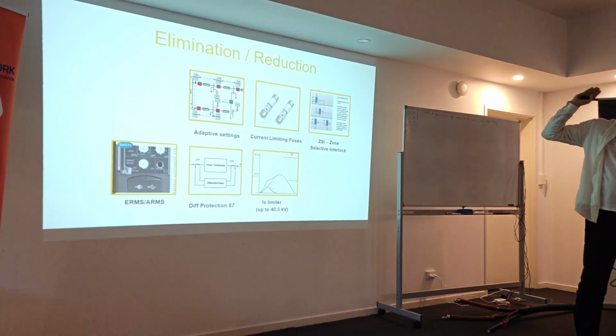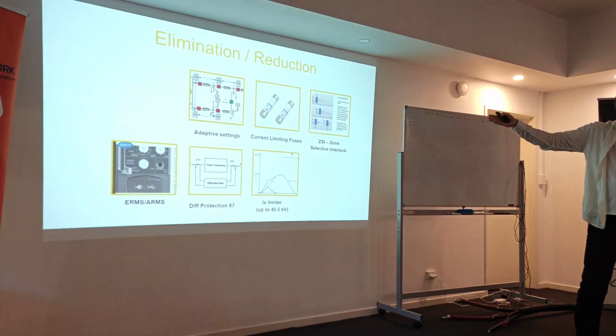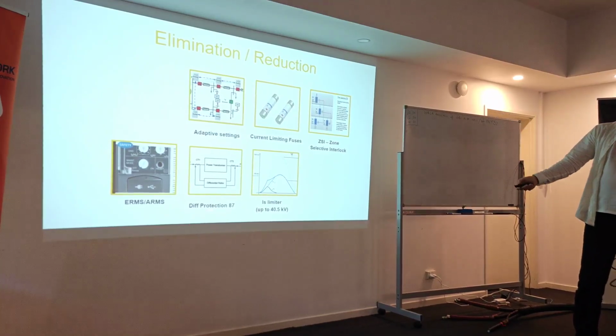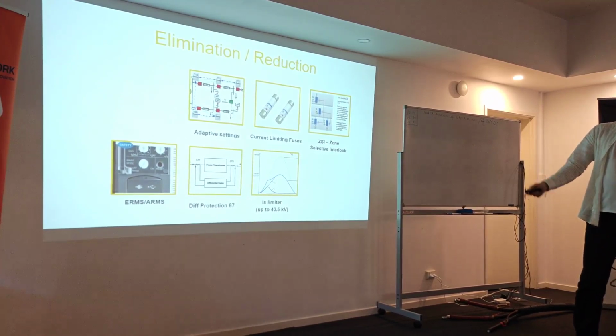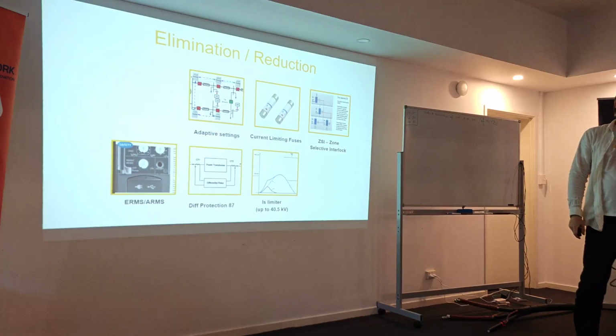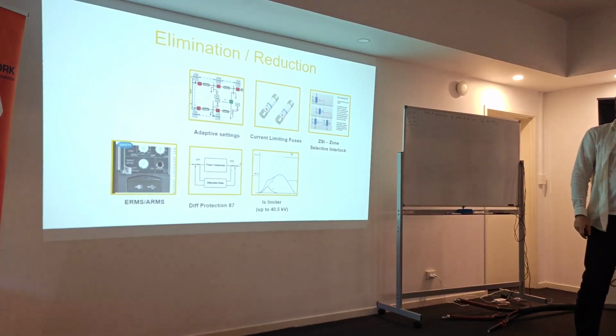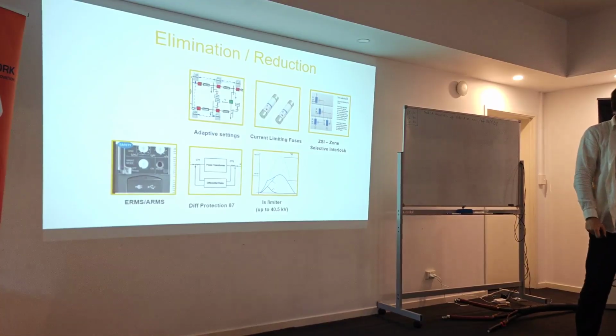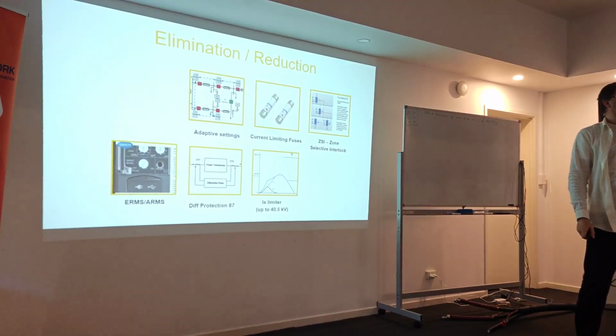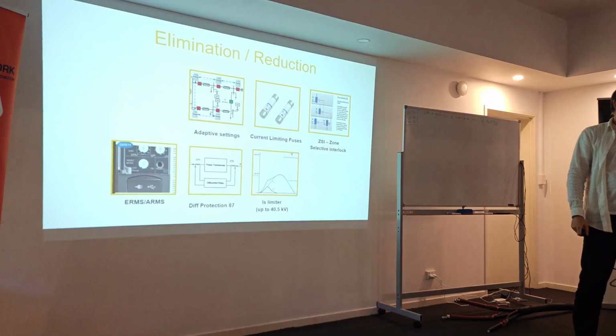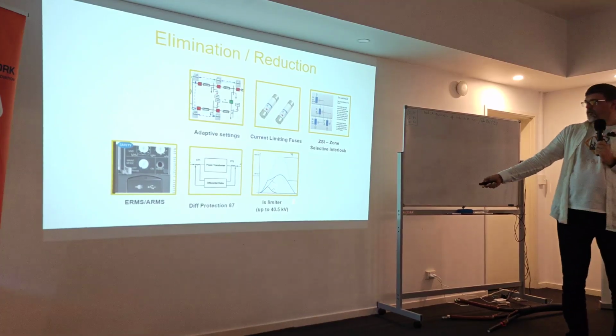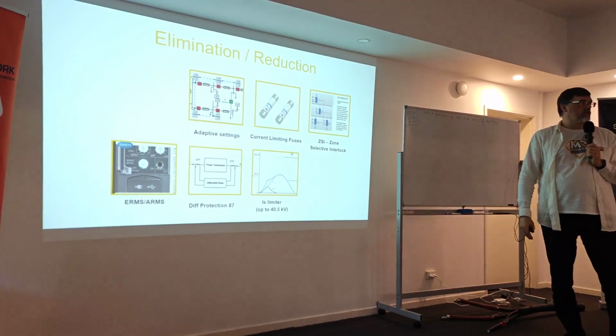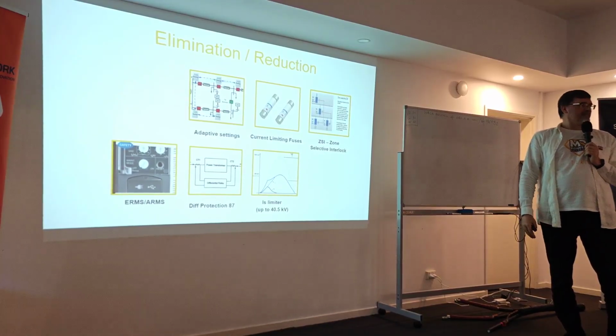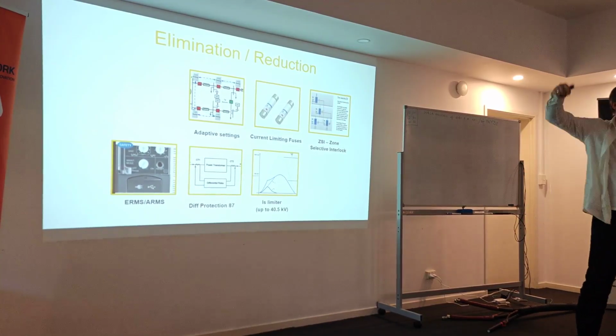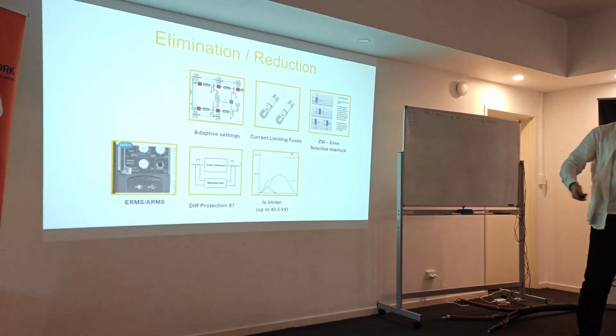Current limiting fusing is just the current limiting fuse. It is just the device that we can use sometimes. Differential protection is nice to have. IS limiter is an ABB thing on the medium voltage. This is a very expensive, smart fuse, which works very, very fast and is limiting the current on the medium voltage systems, which is mainly used on ships because it's so expensive. As far as I remember, I think one field, this thing costs 100,000 euro, which is like pretty much no one will, and on those ships you usually have 2 supplies and you have to limit it and so on.